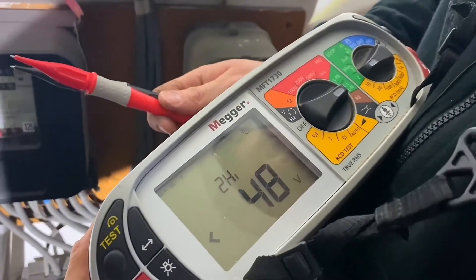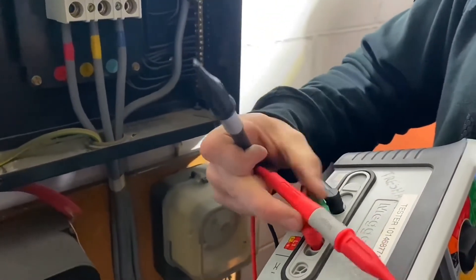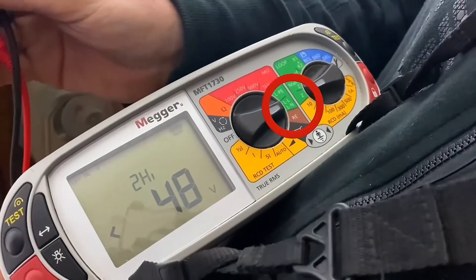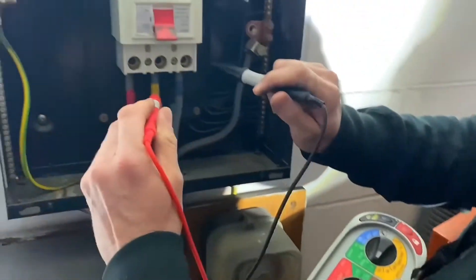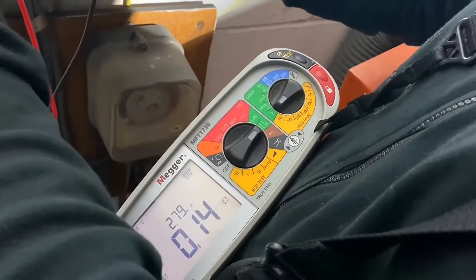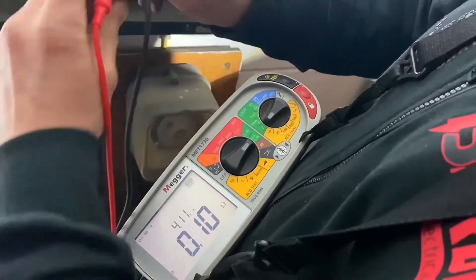So we've kept the instrument in the same position here, but we're actually now going to be testing between the two line conductors. This time it's important to use the correct setting - it's just set on the two lead high, and it says L and L. So we just probe on. Between phase one and phase two, you can see it picks up the voltage - that's 328. We'll go between phase two and phase three - that's 279. And then between phase one and phase three - that's 411.